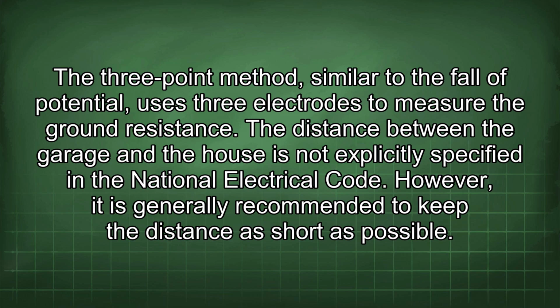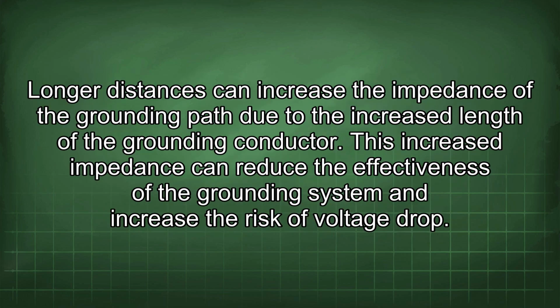The distance between the garage and the house is not explicitly specified in the National Electrical Code. However, it is generally recommended to keep the distance as short as possible. Longer distances can increase the impedance of the grounding path due to the increased length of the grounding conductor. This increased impedance can reduce the effectiveness of the grounding system and increase the risk of voltage drop.